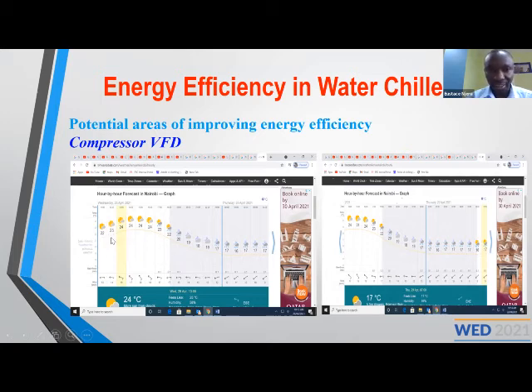This is a graph showing the temperatures of Nairobi on one of the days, 29th April 2021. You find that at around 2 to 3 p.m., the temperature was 24, but at 2 a.m. in the morning, it had reduced to 16 to 17. If this was a data center operating the whole day and night, you find during the day the cooling load is higher, so to optimize the cooling load you need to employ a VSD to control either the pumps or the compressor and so on. You need to be reducing, as long as you work within the 20% we have talked about.